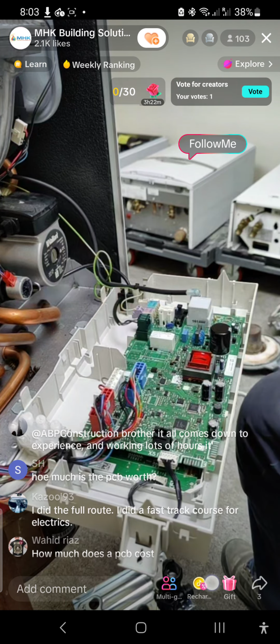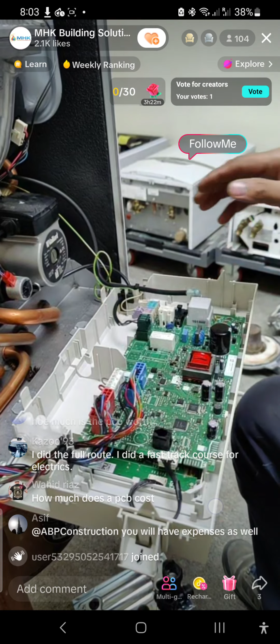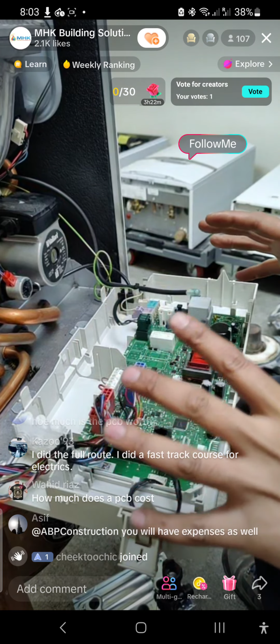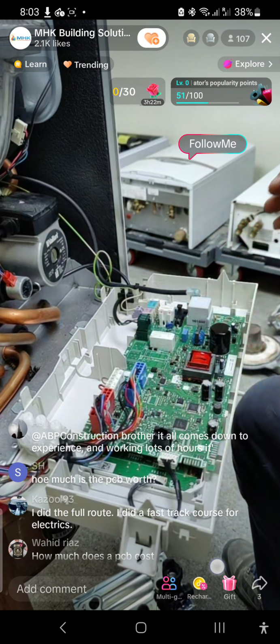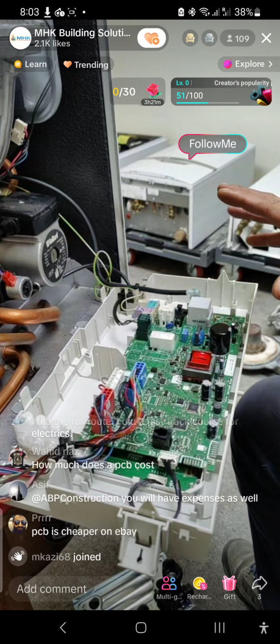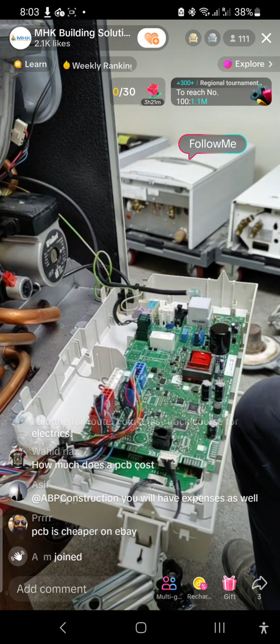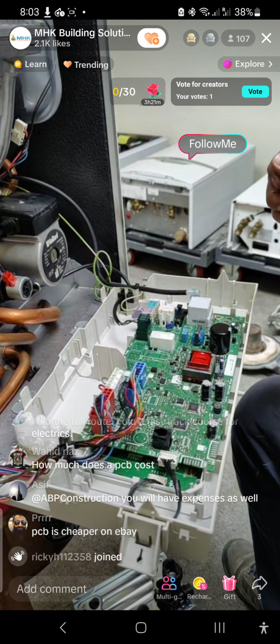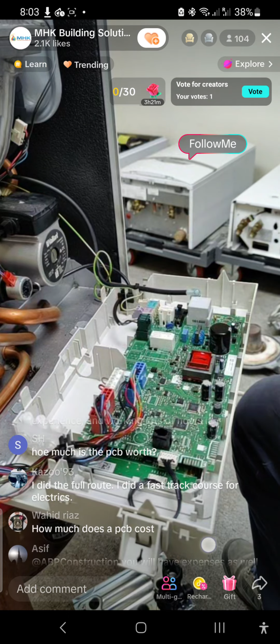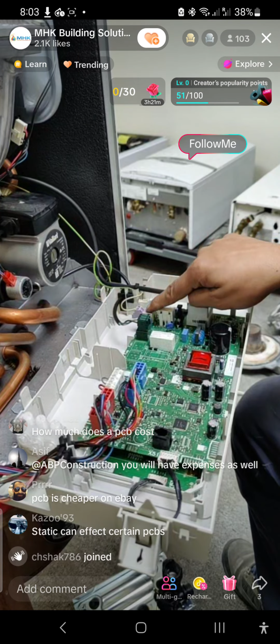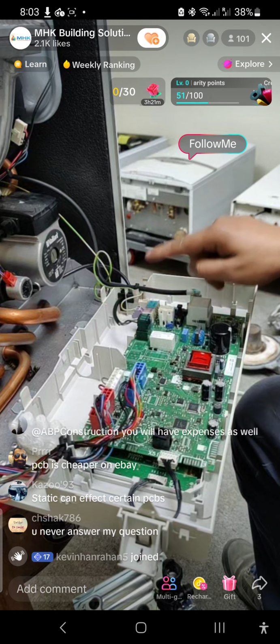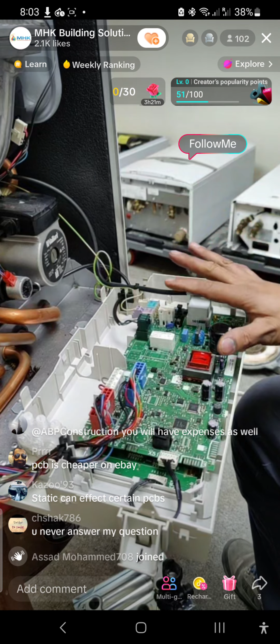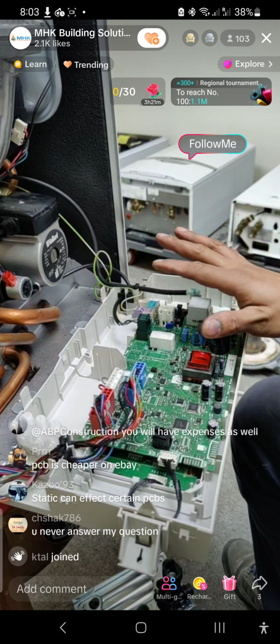Okay, guys, let's just change this PCB then. Let's have a look. So obviously, to get to this far, your boiler needs to be safely isolated from electricity. I can't stress that enough. Under no circumstances be tempted to work live. Make sure you've turned your fuse spur off, you've removed the fuse, you've proved dead to make sure there's no power coming to it. Make sure you've done all of that.